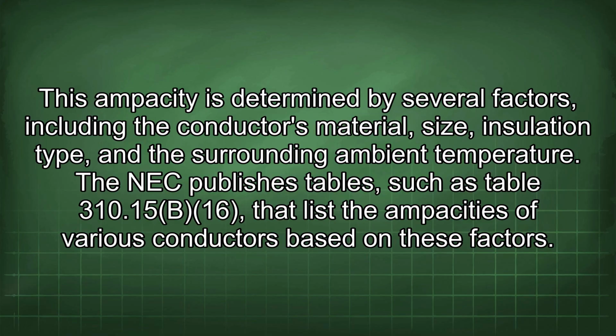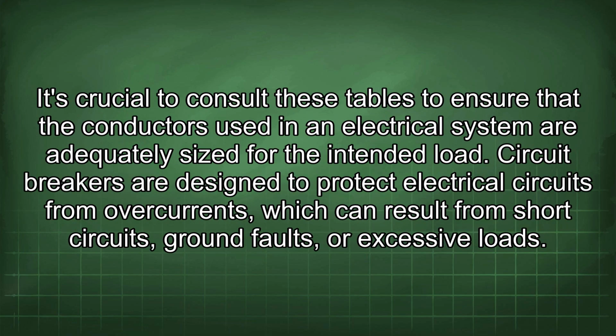The NEC publishes tables, such as Table 310.15(B)(16), that list the ampacities of various conductors based on these factors. It is crucial to consult these tables to ensure that the conductors used in an electrical system are adequately sized for the intended load. Circuit breakers are designed to protect electrical circuits from overcurrents, which can result from short circuits, ground faults, or excessive loads.